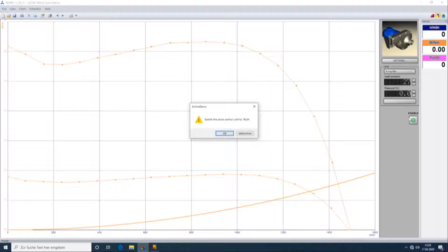If I start the motor now, we see the working point comes across both characteristics, between the ventilator and the torque line of the motor. If I move to delta, I see the behavior. Normally, this behavior is shown on the whiteboard, drawing all the lines, and you have to believe that the working point is exactly at that point. But with the hardware here, you can do it in an experimental way, which helps the student to understand the interaction between both systems. Now the question is why we use star-delta connection. Star-delta connection is used to reduce the inrush current of motors.